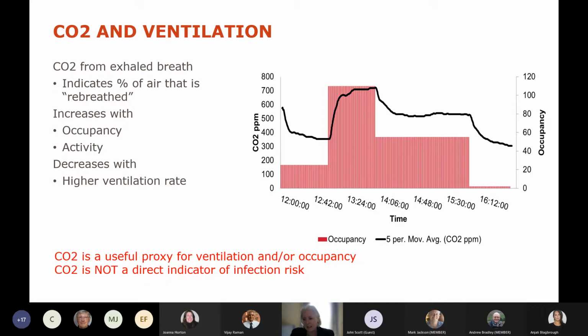The graph on the right shows a mechanically ventilated lecture theatre. The black line is CO2, the pink bars are occupancy, and you can see a very nice trend because it's a well mixed space, where CO2 increases as occupancy increases. As we reduce the occupancy, you get a decay to a new steady state, and then as you decrease it again, you get another decay.